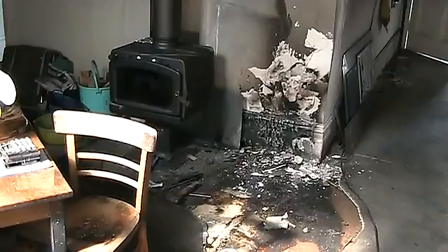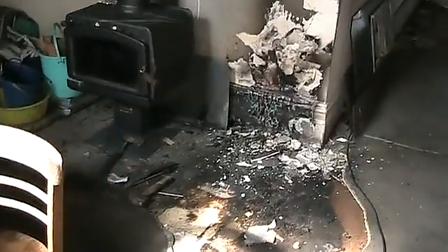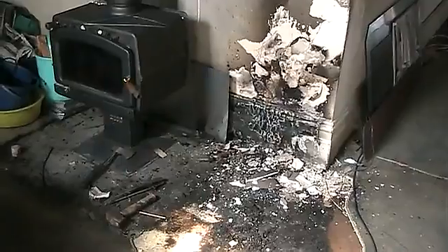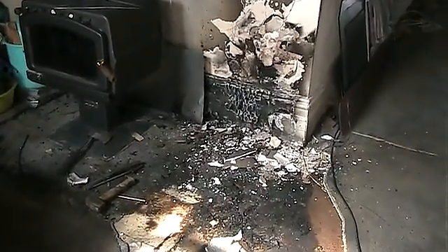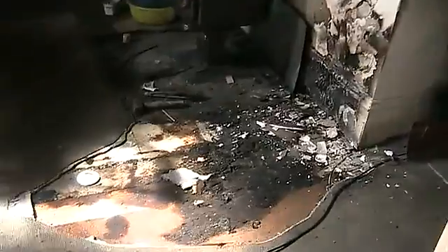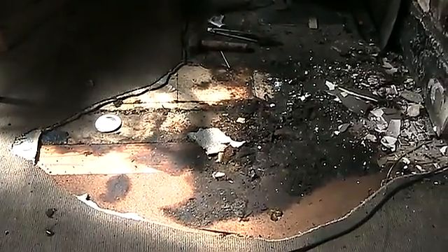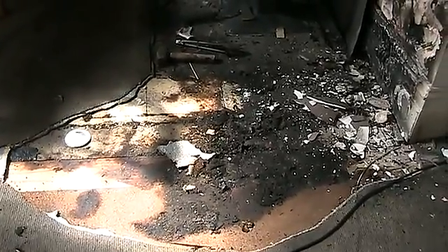When I got back, it appears the batteries had already exploded and set fire to this room in at least two places. The primary seat of fire was here, producing an awful lot of black smoke, and it burnt the entire casing of a 12-volt lead-acid battery that was sitting next to it — though that was not connected to anything at the time. There's an area of burnt carpet that has been cut away, and evidence of heat damage to the particle board underneath. Over the top half is concrete, with some old vinyl tiles there as well.